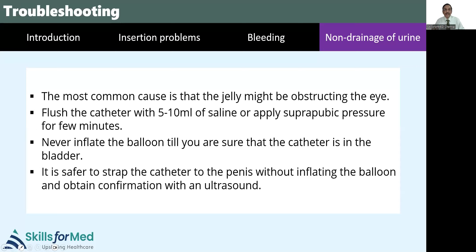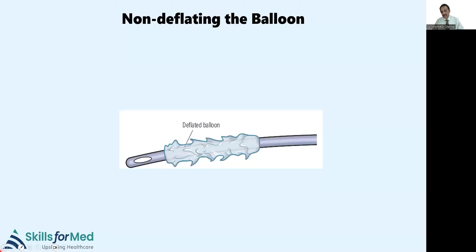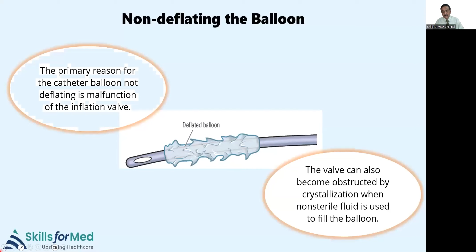Now, this is when you are going to remove the catheter. The most common problem is that the balloon will not deflate and you cannot pull out the catheter. The primary reason is malfunctioning of the inflation valve, or sometimes you put some other solution like normal saline into the balloon instead of water, and this crystallizes and causes wrinkles like this. So the catheter will not come out. This you have to avoid.